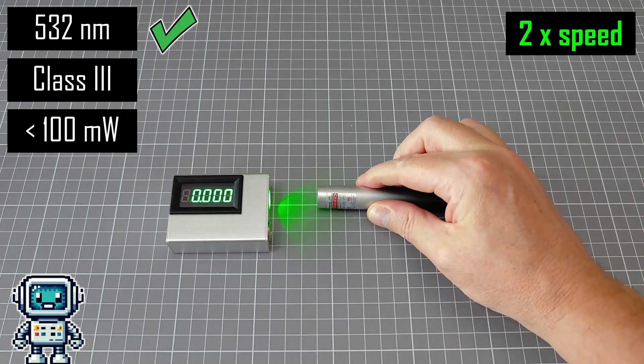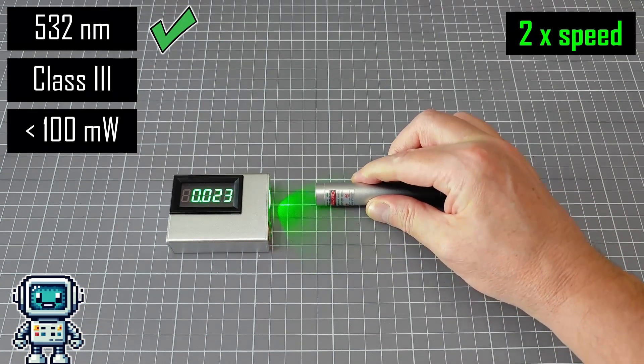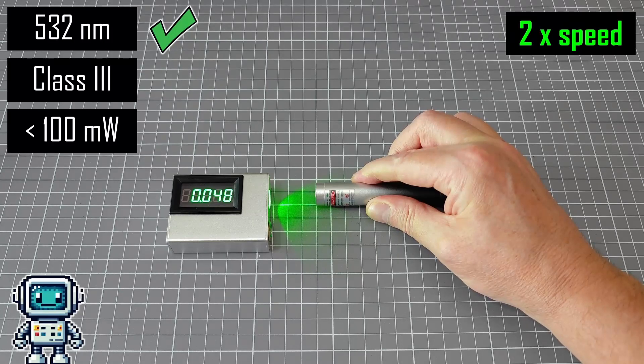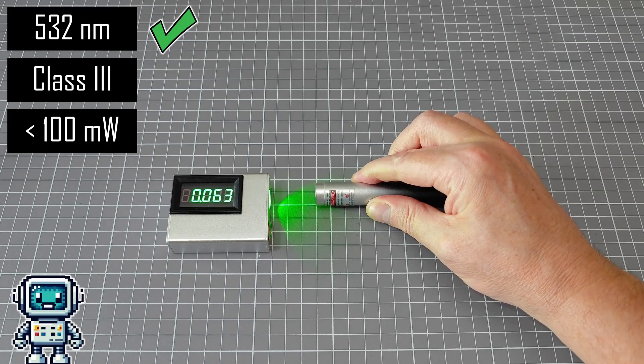Indeed, using this spectrometer, we can see that the main emission line is correct. The instructions say this device needs about 5 seconds to get a stable reading, but we found it took at least 20 seconds to stabilize. In the end, this instrument finally stabilizes at a value of about 65 milliwatts.